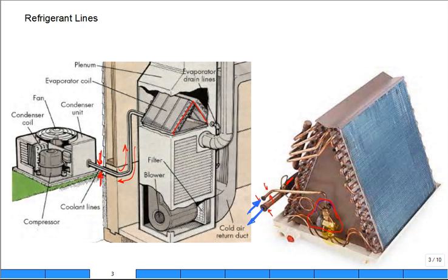But once it goes, now it drops the pressure right across here, and now you have a distributor. So, it's got one, two, three, four lines, and they snake over, and they start feeding sections of the coil, and it goes back, do a loop back, do a loop back, do a loop. So, you can see these 180-degree elbows that redirect the flow back and forth in a serpentine path through the coil, and it's all finned on this side to promote heat transfer.